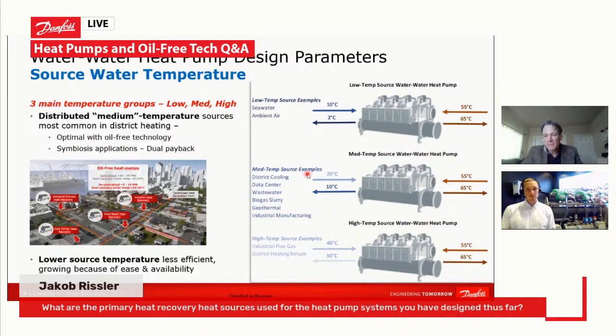Then you have the medium temperature heat sources, and in general these are what we call the symbiosis applications. What I mean by symbiosis is the way we look at it: every chiller is a heat pump, and every heat pump is a chiller. It's just a matter of how much you're lifting the temperature in terms of the cooling and heating provided, and whether or how you're making use of that heating. In this category, most are those symbiosis applications where you're making use of both the cooling and the heating.